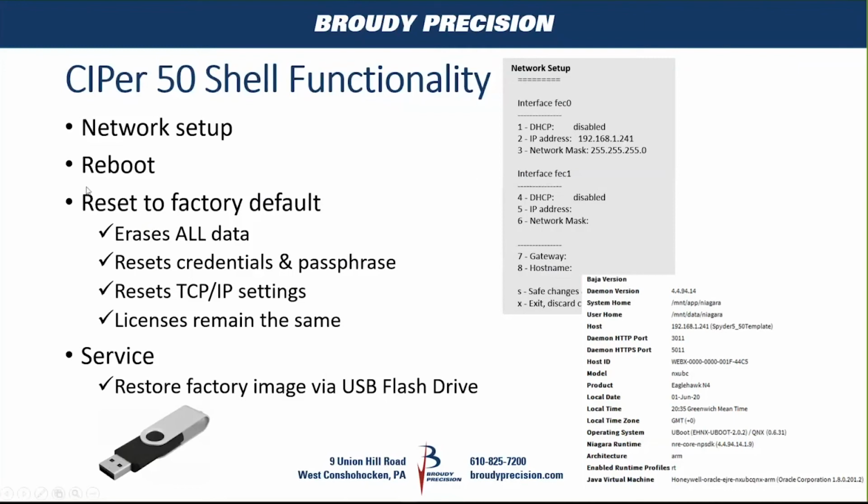Another feature in there allows you to reset to factory default. All that means is it wipes out the Jace as far as your modules, your station, everything's gone, resets your credentials and your passphrase, and resets the TCP settings.